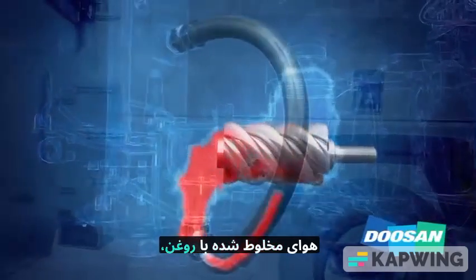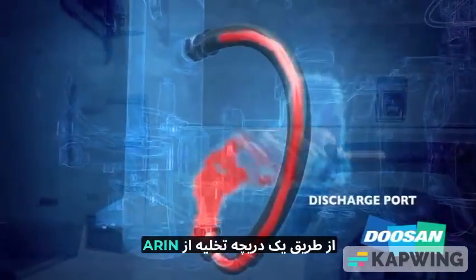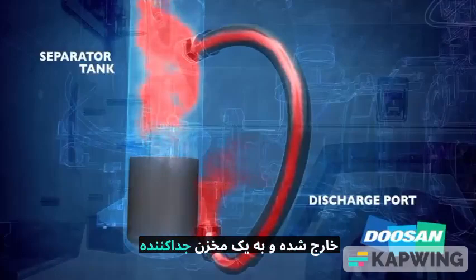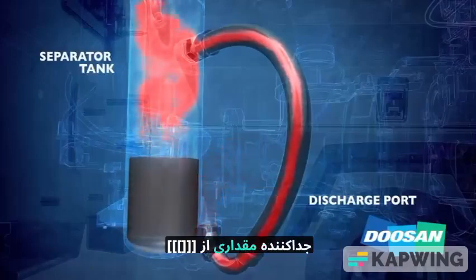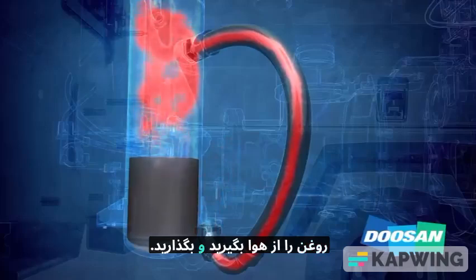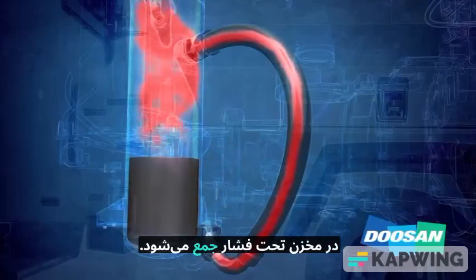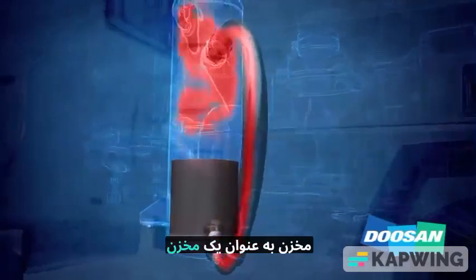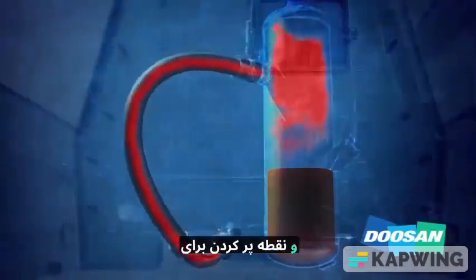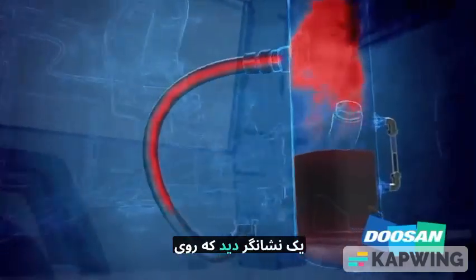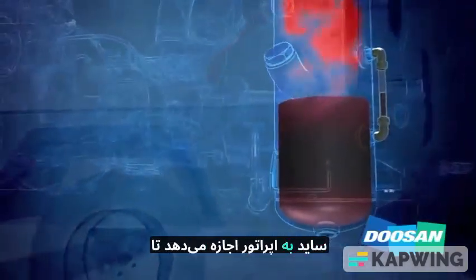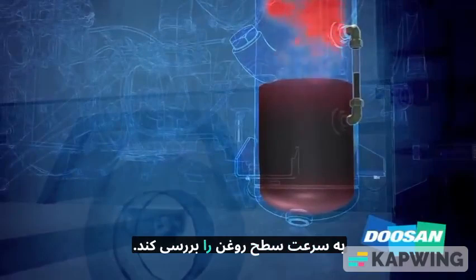The air, now mixed with oil, exits the air end through a discharge port and is piped to a separator tank. Here, the separator will remove some of the oil from the air and let it accumulate in the pressurized tank. The tank acts as a reservoir as well as an oil service and fill point for maintenance. A sight gauge mounted on the tank's side allows an operator to quickly check the oil level.